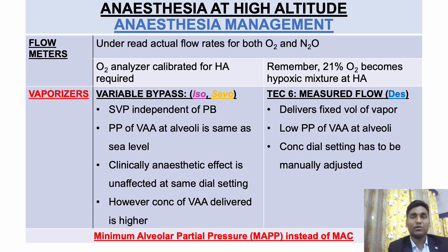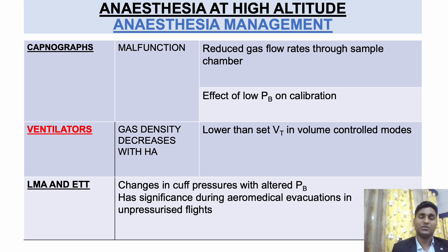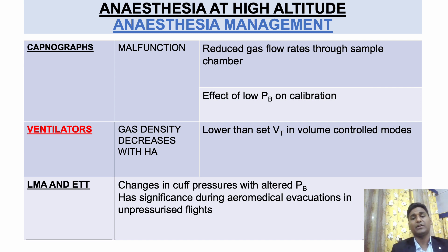For desflurane, however — which I do not use at this altitude — it delivers a fixed volume of vapor, so lower partial pressure is delivered at altitude and the concentration dial must be manually adjusted. The concept of MAC changes at higher altitudes: it is minimum alveolar partial pressure rather than minimum alveolar concentration. Capnographs malfunction at higher altitude mainly due to low barometric pressure effects on calibration and reduced gas flow through the sampling chamber — always get an ABG to know baseline CO2. Ventilators in volume control mode deliver lower tidal volumes due to decreased gas density.